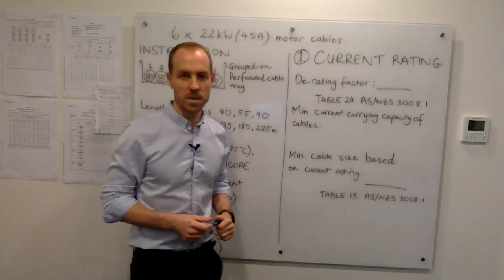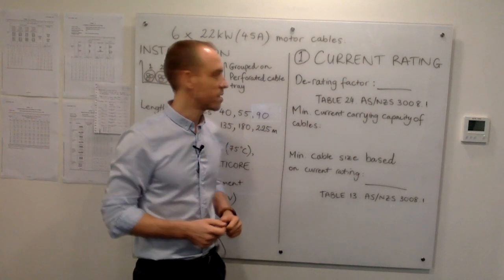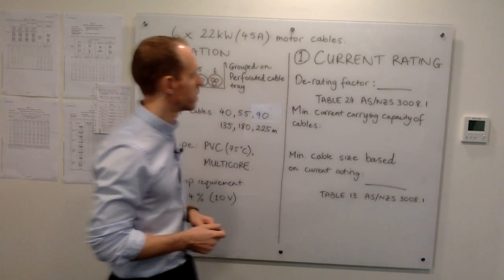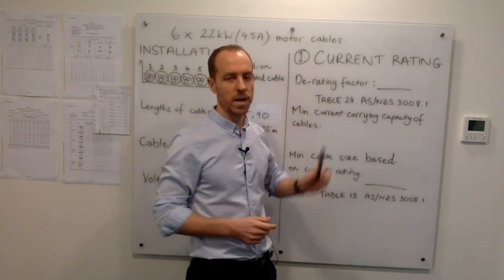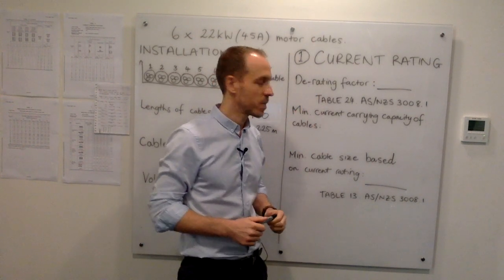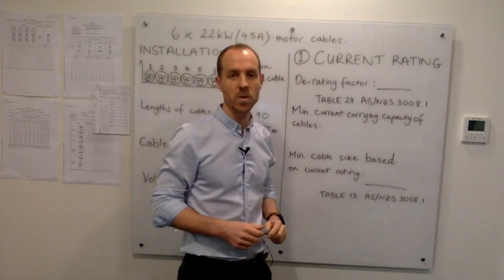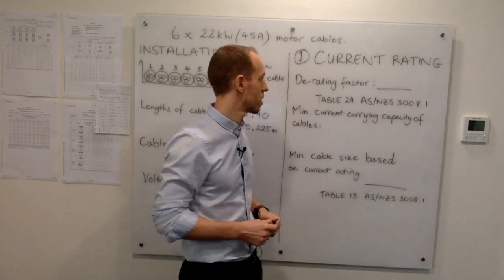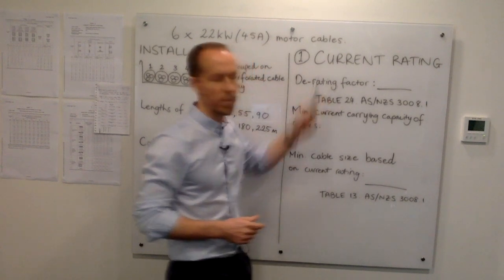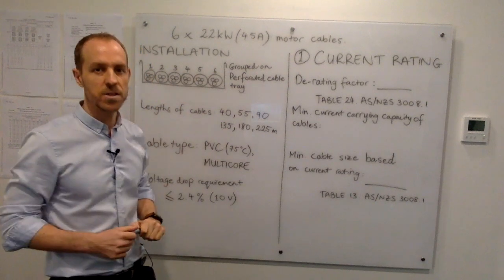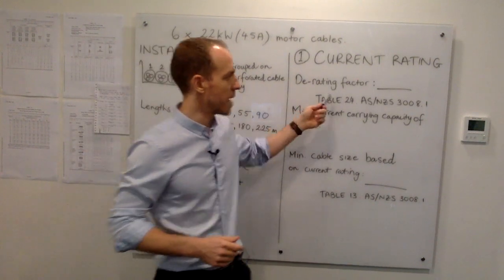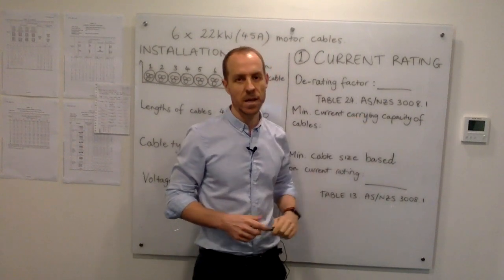The first step is to work out the minimum conductor size based on the required current rating. We're going to need a derating factor to work out the minimum current capacity required for the cables. So we're going to look up a derating factor for this installation condition, referring to table 24 in AS3008.